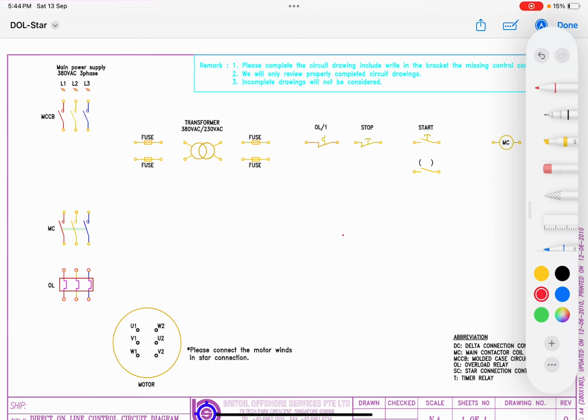First of all, we can see that on the top we have the main 380 volt 3-phase power supply. We are going to connect this MCCB, which is your molded case circuit breaker, from your mains to the breaker inlet. So we connect it like this, and your main power supply is available at the inlet of your circuit breaker. Now the circuit breaker is in open position, so we are going to close it. As soon as we close the circuit breaker, power supply from the MCCB will go to your magnetic contactor.